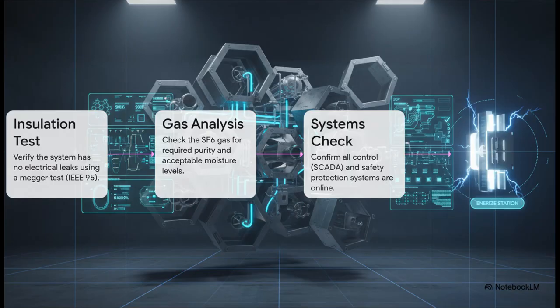So bringing the station to life is a super careful, step-by-step process. You run final checks on the insulation. You analyze the gas one last time to make sure it's pure. You test every single control and safety system, the whole SCADA network, to make sure the brain is talking to the body. Only when every single box is checked do they finally give the command to energize.